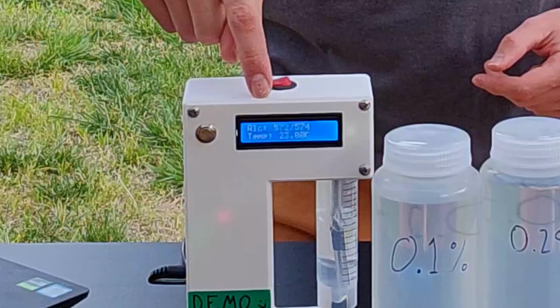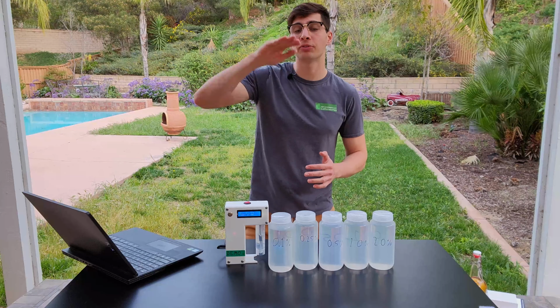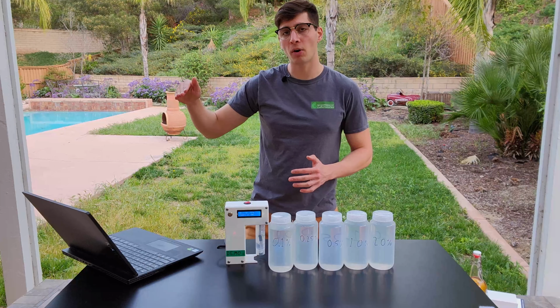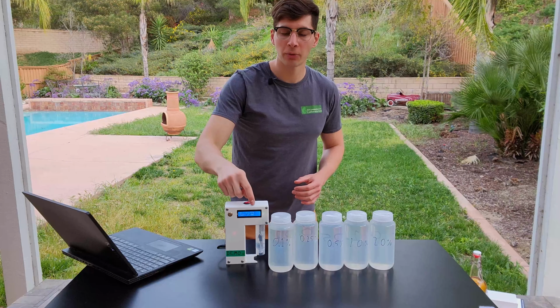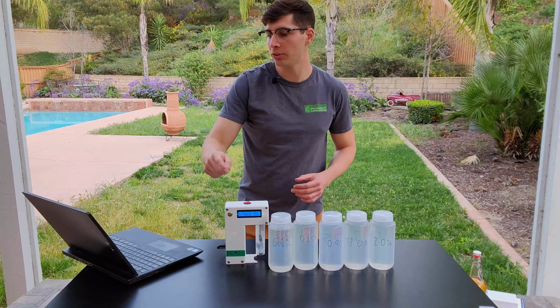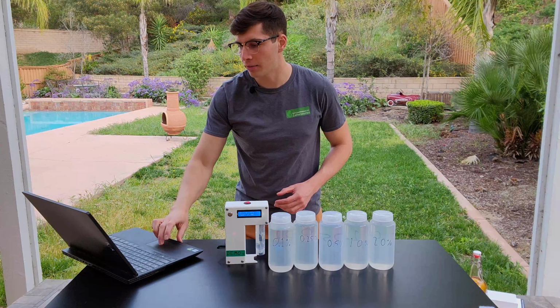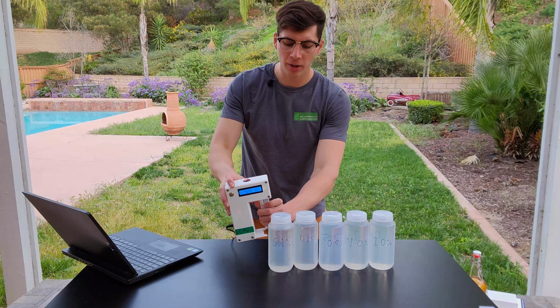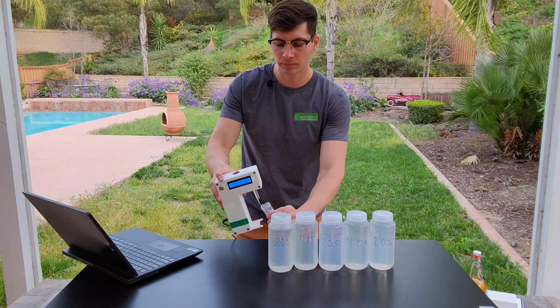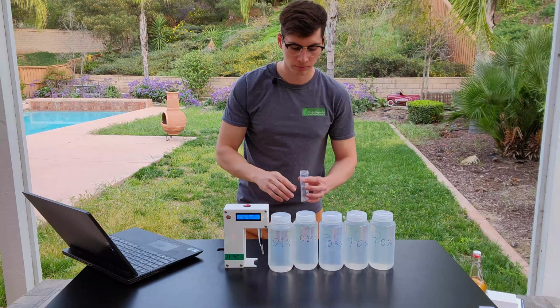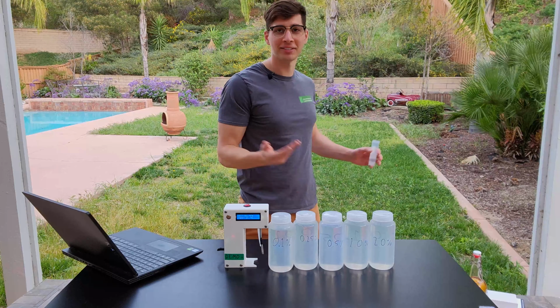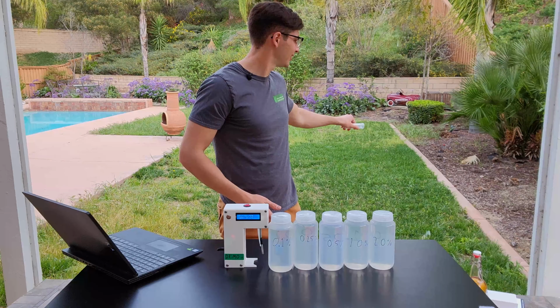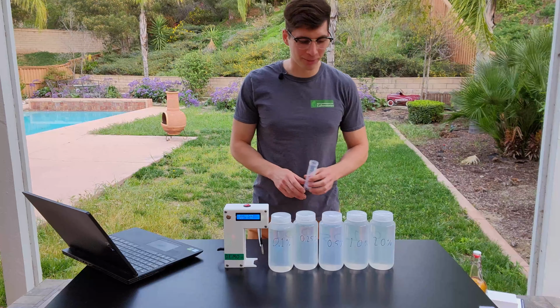So you can see now the reading on the right is higher than the reading on the left, and that means it sort of reached that plateau and it started to fall back down again. So we're looking at a reading of about 574, so I'll now enter that into our graph. So now we can take this sample out and throw it away. I mean, it's alcohol and water. We'll water the yard with these samples.